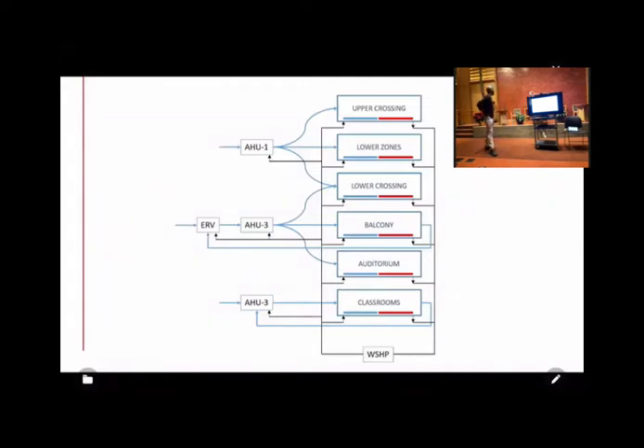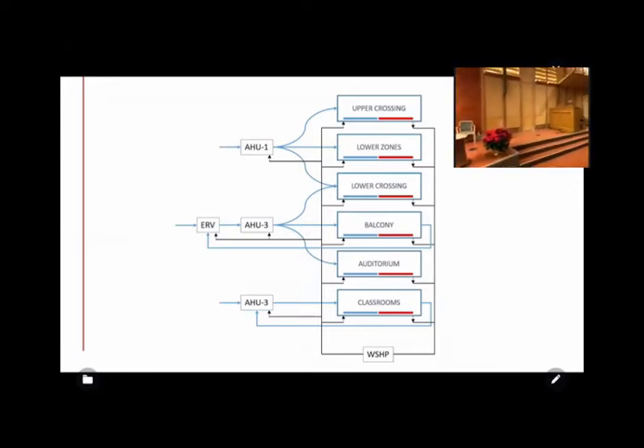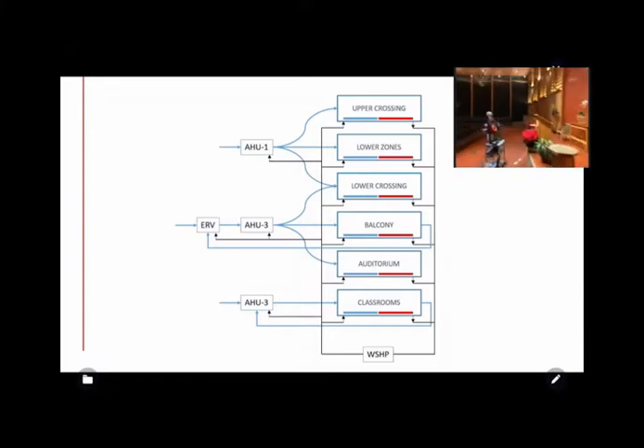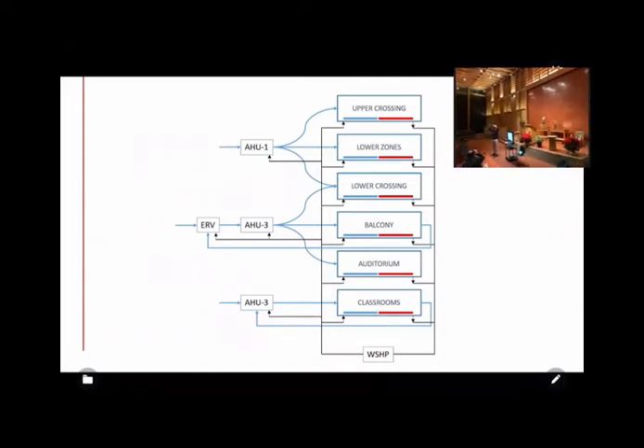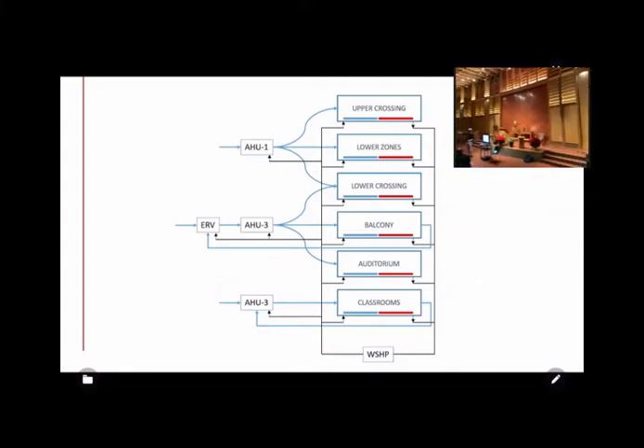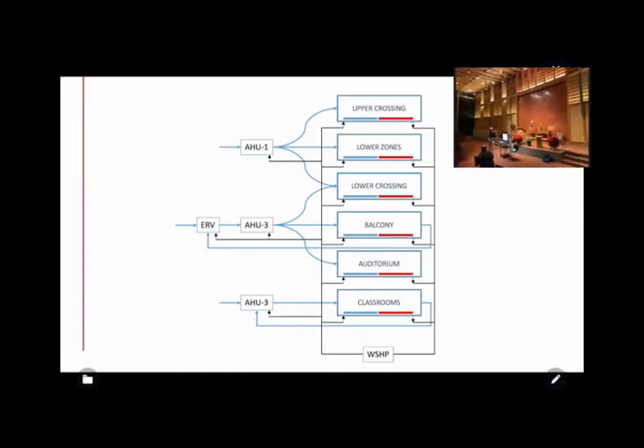But you see these louvers that are along low in the wall here. There was a desire to have this space particularly be naturally ventilated, but it doesn't lend itself well to natural ventilation. Even though it's got some nice height, which you need, it's very hemmed in on all sides by trees and other buildings. So there wasn't going to be much opportunity. Plus there's a lot of unused volume. And the question was, how do you get natural ventilation that's going to behave itself and stay low here, but then also not make it stuffy for the people up in the balcony?